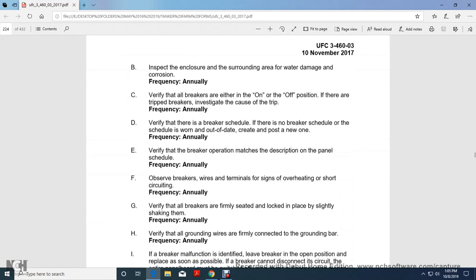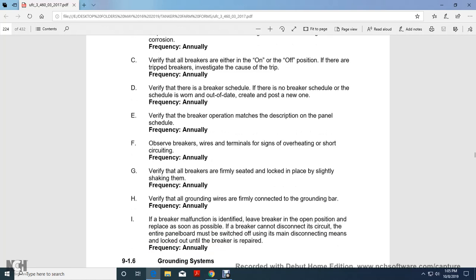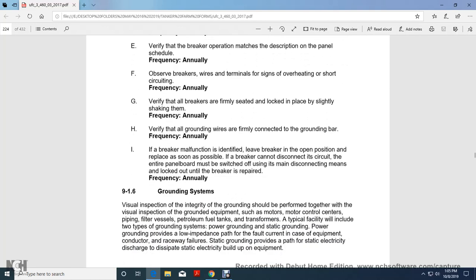Verify that the breakers are scheduled, with no schedule or a worn-out schedule being replaced with a newly created one, annually. Verify the breaker operation matches the description on the panel schedule, annually. Observe breaker wire terminals for signs of overheating and shorting circuits, annually. Verify all breakers are firmly seated and locked in place by slightly shaking them, annually. Verify all the ground wires are firmly connected to the ground bar, annually.